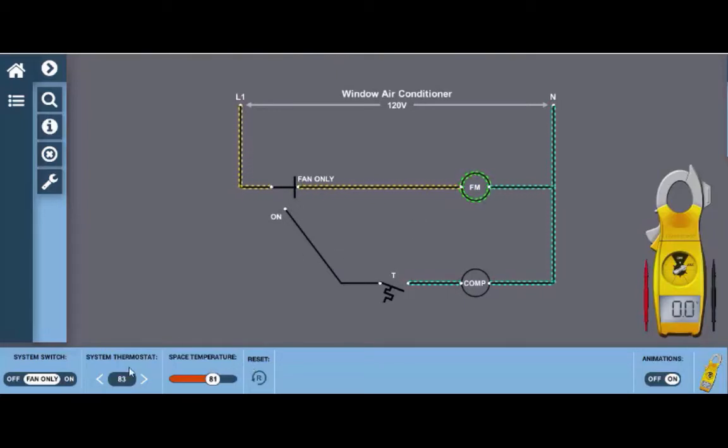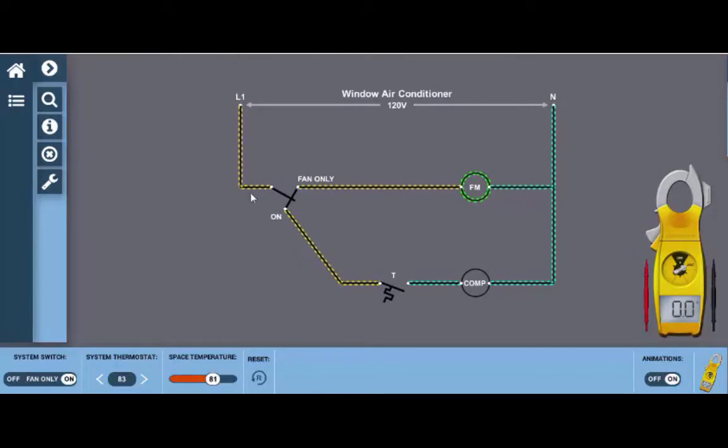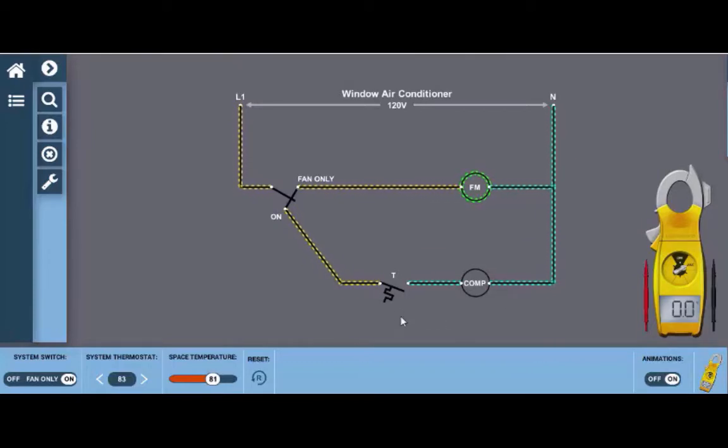In addition, we can turn it to the on position which will close contacts to both the fan motor and to the compressor circuit. Now currently we see the compressor is not on because the thermostat is in series to it and the thermostat is not calling for cooling currently.